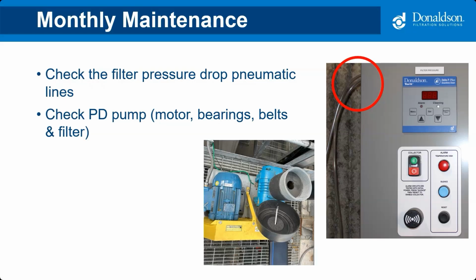Another thing to take note of is, if your dust collector has a variable frequency drive, which I just call basically a fan speed controller, a lot of those are driven off of the reading from these lines. So if those lines are plugged or leaking, your fan control isn't going to know what to do. So it's really important these lines are airtight and in good condition.